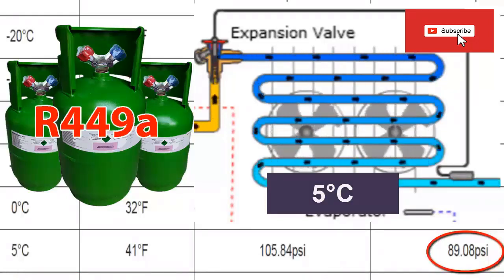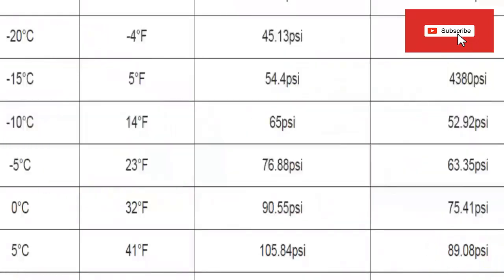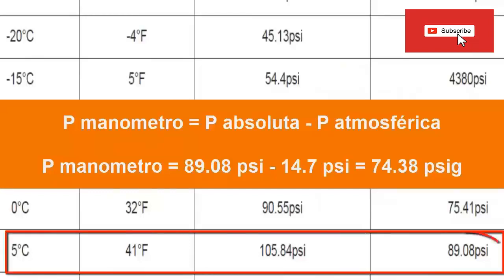As the pressure in the table is given in absolute values, you must subtract the atmospheric pressure of your location from these values. 14.7 psi can be taken as general atmospheric pressure. Thus, 14.7 psi must be subtracted from 89.08 psi to obtain a gauge pressure value of 74.38 psi G.